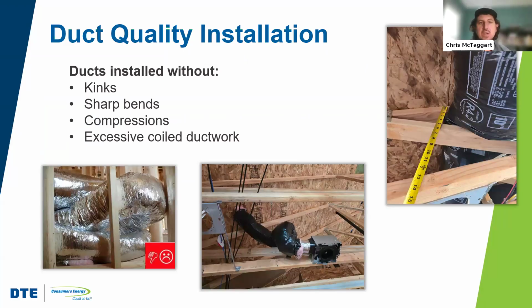Okay, so duct quality installation. So going back to the methods of qualifying a home, again, you have this Track A method, the rater does HVAC grading, or you have Track B, which is the installing contractor is credentialed by an HQITA organization. Regardless of which track you follow, the program has certain mandatory requirements as it pertains to HVAC systems. Installing ducts without kinks, sharp bends, compressions, or excessive coils is one of those requirements. I'll say it's a lot harder to screw this up with sheet metal ductwork.